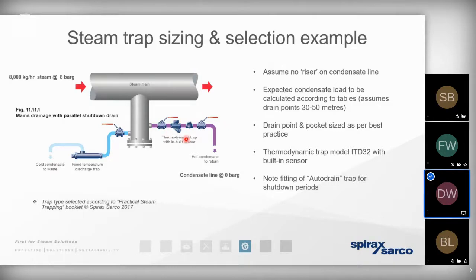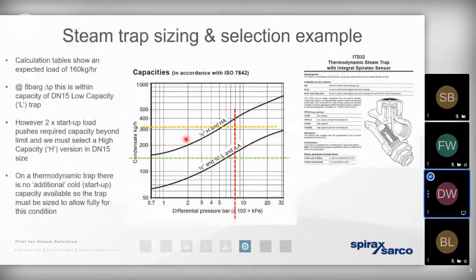trap. So let's look at the trap sizing example for the TD or thermodynamic trap. We know that's the best choice for this application because it's being used on the distribution network. And if we're distributing 8,000 kilograms per hour of steam, if we use that 2% rule of thumb to calculate the running load, we know that we need to remove 160 kilograms per hour. So where the green and red lines intersect, that's where we size the steam trap for the running load.